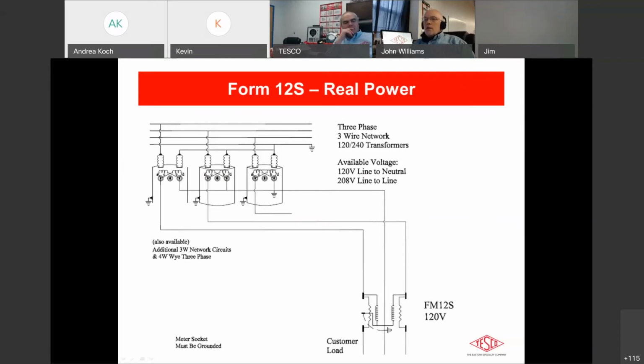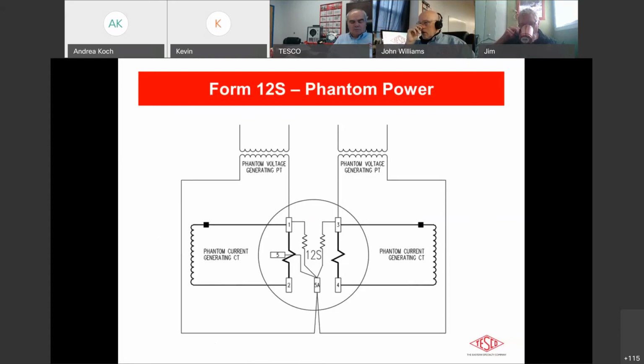All right, so the next one up is the self-contained 12S meter. This one is typically applied in the network configuration, where you have basically the top of a 4-wire Y directly in through the meter into the customer load. Again, you have 208 phase to phase, 120 from line to neutral. And then the test board arrangement, similar application as before, 2 PTs, 2 CTs into the meter. This is one of the simpler ones to apply in the test board.